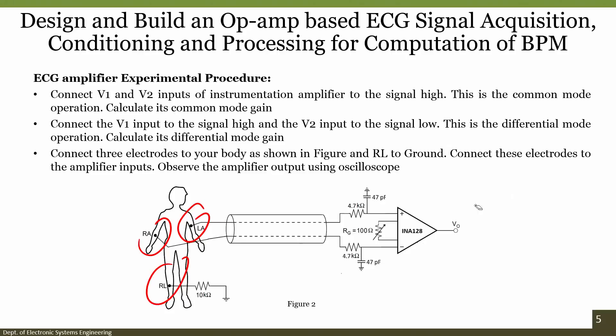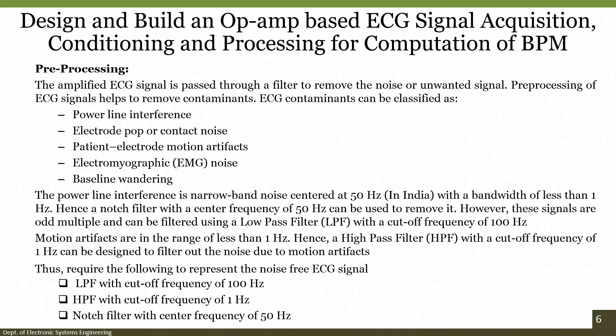Pre-processing is an important part. The amplified ECG signal is processed through a filter to remove noise or unwanted signals. Pre-processing of ECG signals helps to remove contaminants. The contaminants in ECG signals include electrode pop or contact noise, baseline wandering, EMG noise — also called electromyograph — and patient electrode motion artifacts. If the patient is moving while electrodes are connected there is a motion artifact that must be addressed. EMG comes from the muscles; any signal generated from the muscles can be measured with an electromyograph.